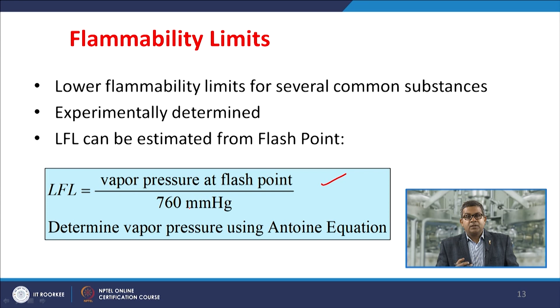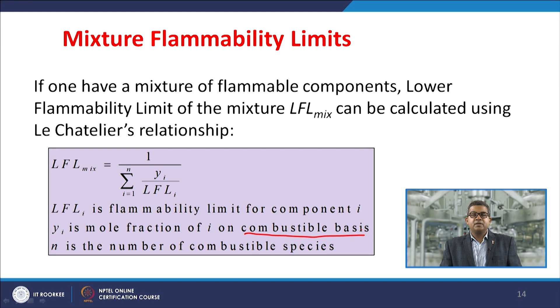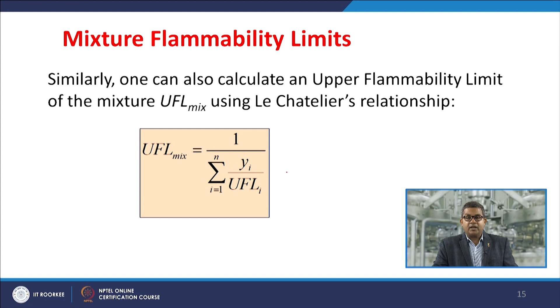Now if one has a mixture of flammable components, the lower flammability limit, or LFL mixture, can be calculated using Le Chatelier's relationship. LFL mixture is equal to 1 upon the summation from i equal to 1 to n of Yi upon LFLi. LFLi is the flammability limit for component i, and Yi is the mole fraction of the ith component on a combustible basis. Remember this combustible basis, because inert material can't be taken into consideration, and n is the number of combustible species present in that mixture. Similarly, you can calculate the upper flammability limit for the mixture using the same Le Chatelier's relationship. UFL mixture is equal to 1 upon the summation from i equal to 1 to n of Yi upon UFLi, with the same designations: the mole fraction of the ith component on a combustible basis.